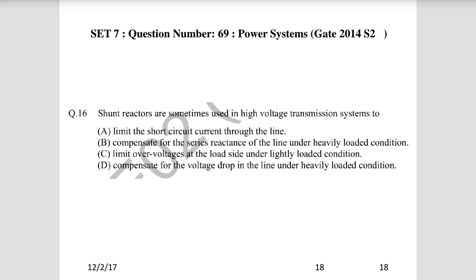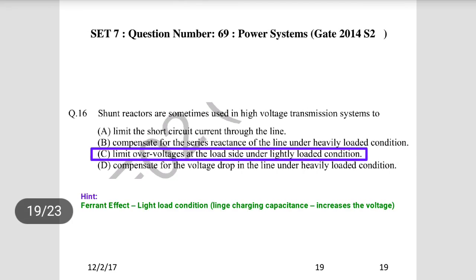Question 16: Shunt reactors are sometimes used in high voltage transmission lines. What is their purpose? As already explained, their purpose is to limit overvoltage at light load or no-load conditions. At light load, due to the capacitance effect, the receiving end voltage becomes higher than the sending end voltage — the Ferranti effect. To avoid insulation damage from this higher voltage, shunt reactors are used.